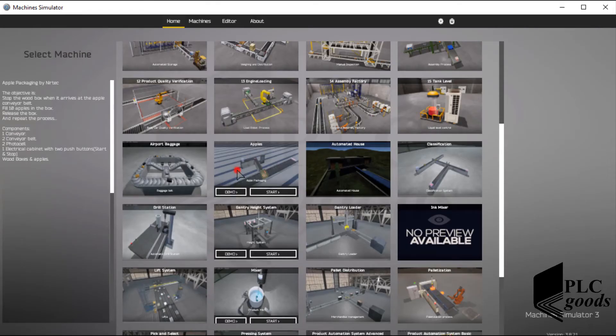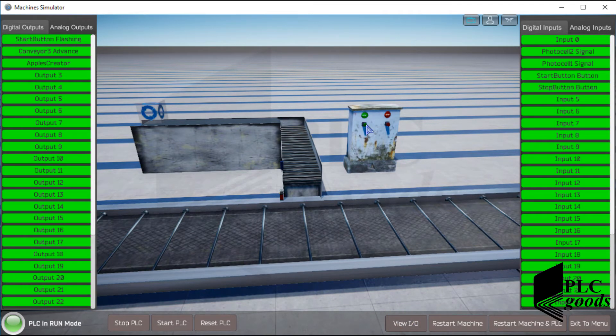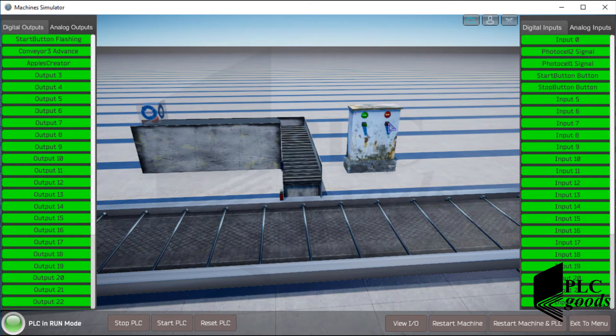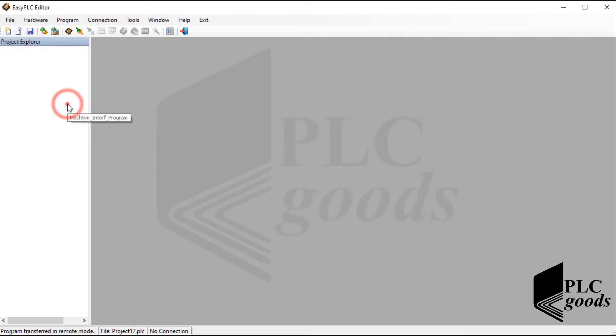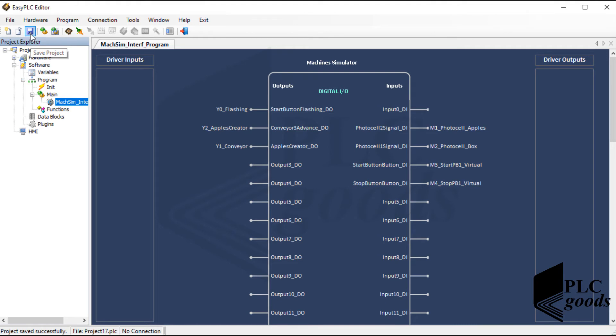Now let's start the Apple project inside Machine Simulator software and test the project. It seems the system isn't working correctly. I've checked my project to find the problem several times. Eventually I found that I need to exchange the place of these two tags, although I believed I had connected my OPC server tags to EasyPLC software correctly. So if you want to connect an OPC server to EasyPLC software, maybe this problem will occur for you. Let's continue to test my project.